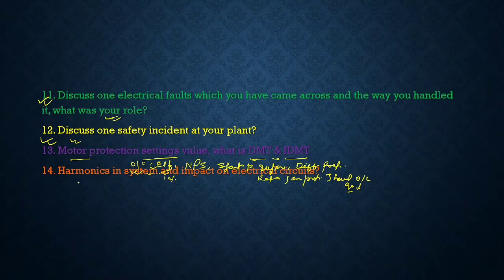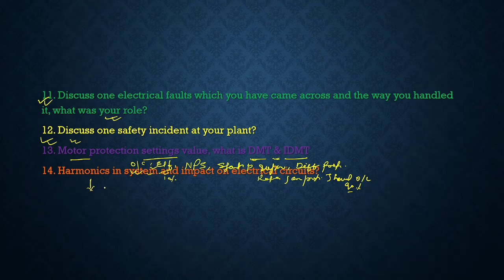The next question was about harmonics in the system and their impact on electrical circuits. What is harmonics? Very important thing again. Since we use many electronic equipment like UPS, VFD, battery charger, where rectifiers and inverters are being used, these are the sources of the harmonics. These harmonics impact our electrical system, like they create double frequency harmonics, which impacts the winding of the motor and generator. So in that way you can tell the interviewer about the harmonics.